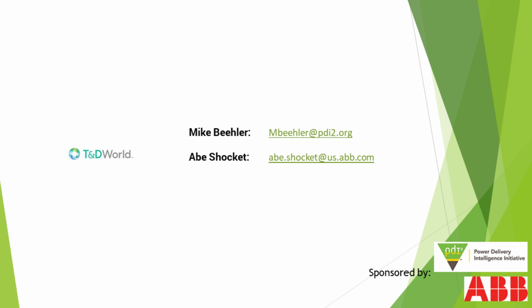So that was the second question, Mike? Well, just in general, I like the topic of SF6 gas replacement, but this one is replacing 27.6 kV SF6 switchgear where fault levels exceed 12.5 kA. Yeah, I think with SF6 gear, oftentimes I see specs from customers that say, here's what my current spec is, can you meet this with your gear? And it's going to say 25 kA for the fault current, and we often can't meet that, particularly at 27 point, whatever this question said, 27.6.